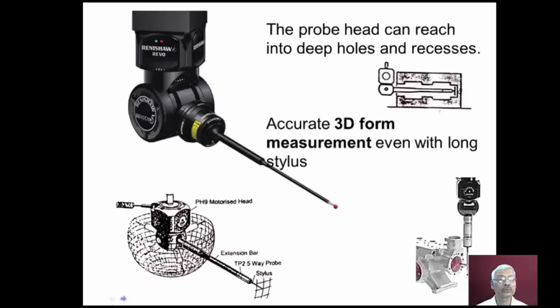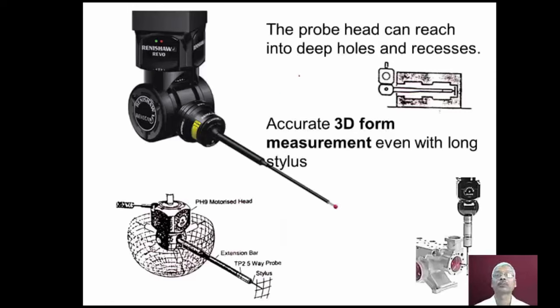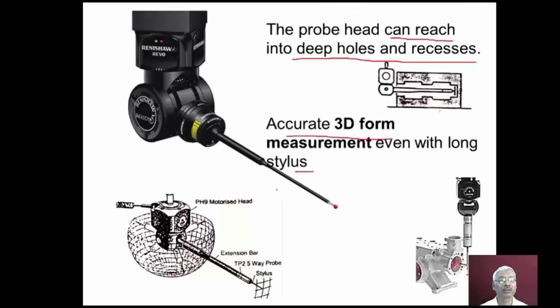With the use of extension bars, the probe head can reach into deep holes and recesses, and internal details of deep holes can be measured. An accurate 3D form measurement even with a long stylus is possible. By using extension bars, the measurement volume can be selected appropriately.